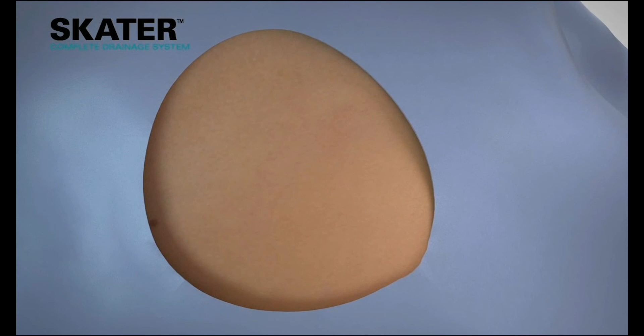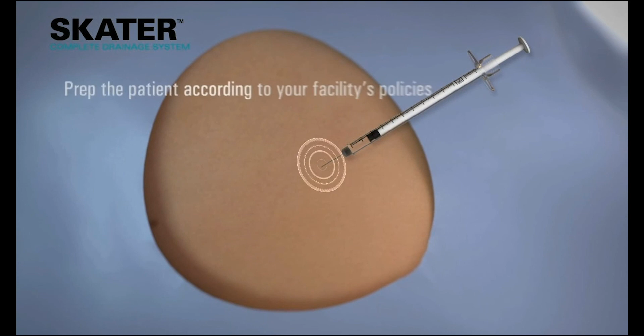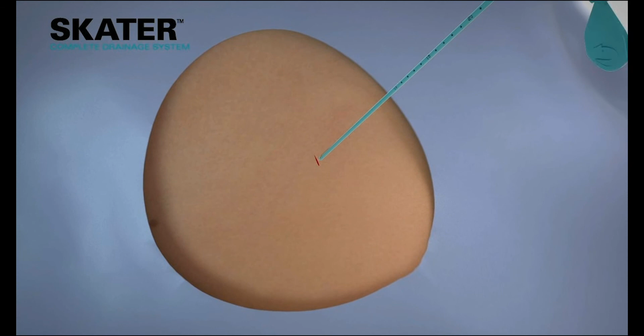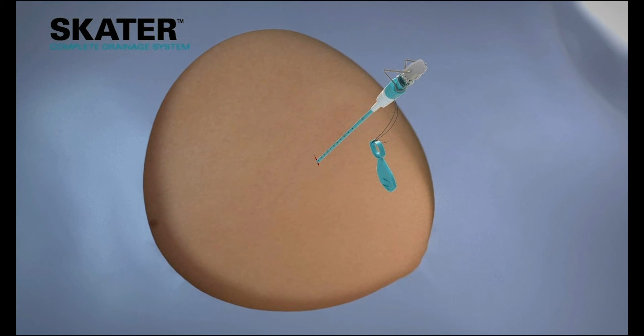The SKATER catheter placement procedure for abscess drainage is conducted under imaging via either the direct stick or over-the-wire method. Once the pocket of fluid has been targeted under imaging, local anesthesia is applied and a skin nick is created to insert the drainage catheter. The assembled catheter, cannula, trocar stylet is advanced into the body using ultrasound or other image guidance. After insertion, the trocar stylet is removed by releasing the Luer lock from the cannula hub. Check that fluid is escaping or aspirate with the syringe to verify placement.